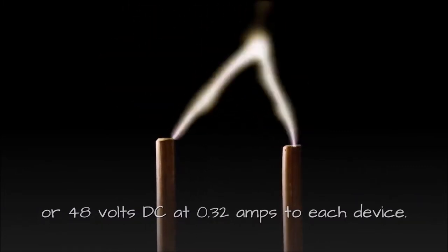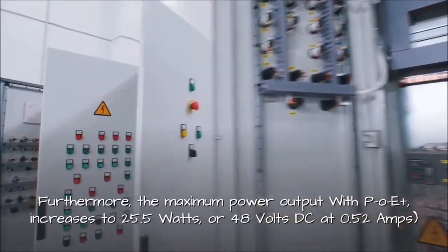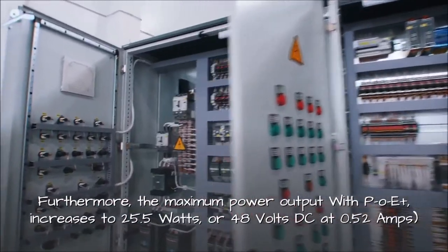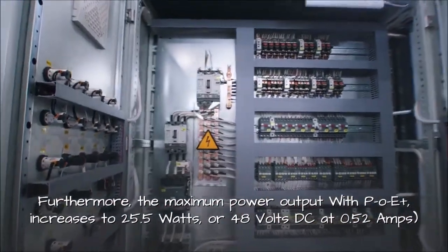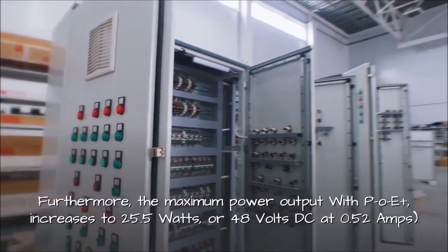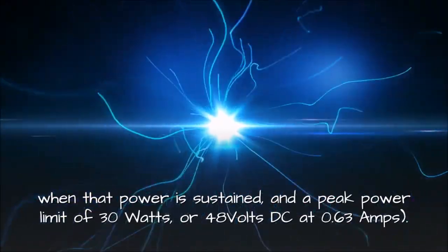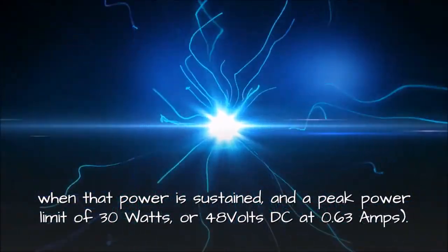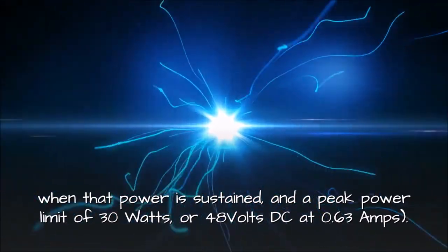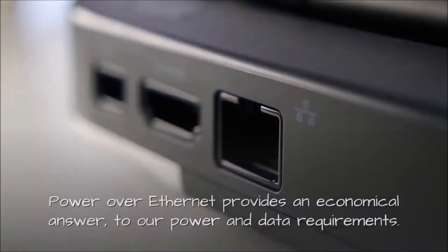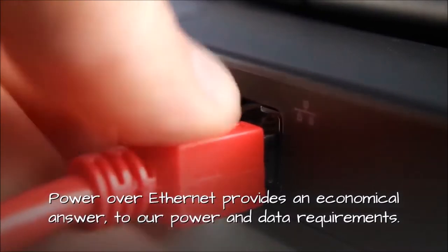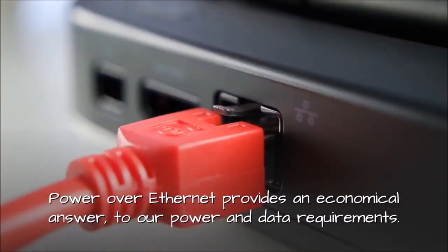each device. Furthermore, the maximum power output with PoE Plus increases to 25.5 watts, or 48 volts DC at 0.52 amps when that power is sustained, and a peak power limit of 30 watts, or 48 volts DC at 0.63 amps. Power over Ethernet provides an economical answer to our power and data requirements.